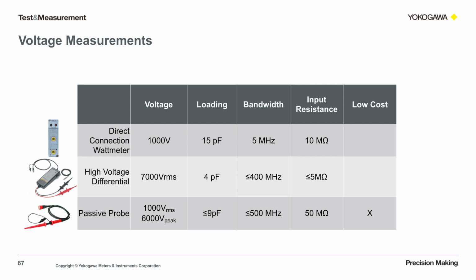Second is a high voltage differential probe. This actually has a differential amplifier in its architecture and subtracts the positive and negative leads. The advantage is it's rated for definitely high voltage and lower loading capacitance. The third is a passive probe. Passive probes are really common throughout labs. They have a high voltage rating, and they're relatively inexpensive with a high bandwidth, but the trade-off is going to be accuracy.